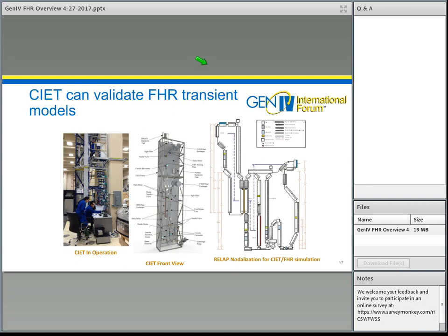One of the things we found is that when you work at low temperature with heat transfer oils, you can use instrumentation that has very high accuracy. For example, pressures around the loop in the CIET facility are measured using manometer lines that can measure pressures to an accuracy of slightly under one millimeter of head.